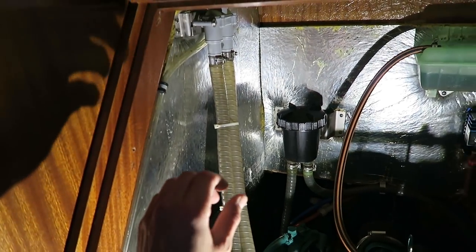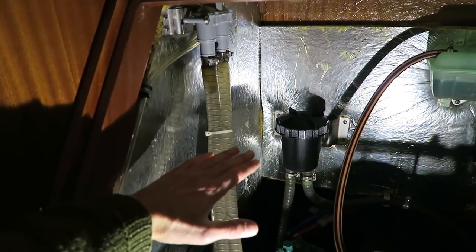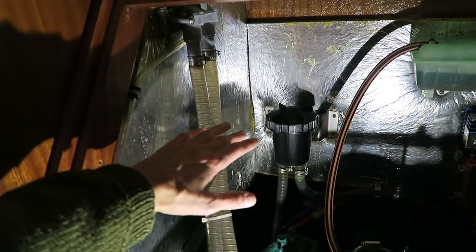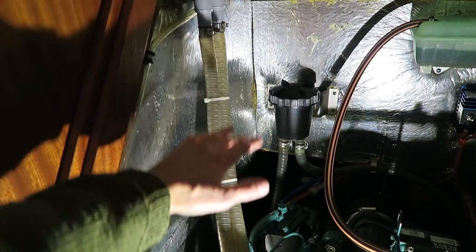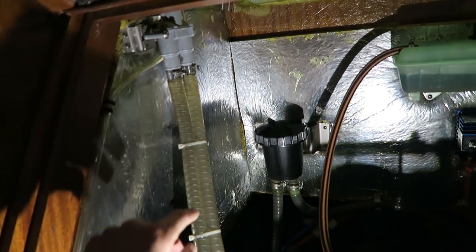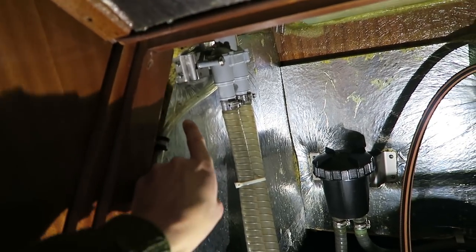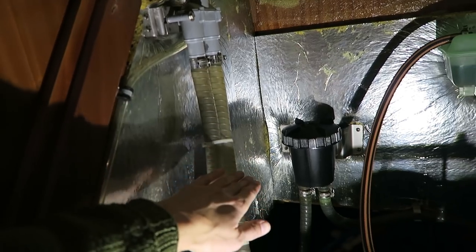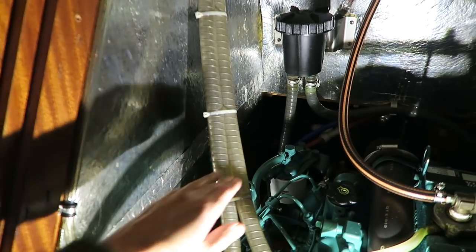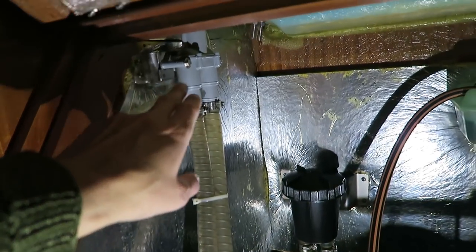When you turn off the engine, both pipes must drain slowly. The siphon valve must then let in some air through the hose and the system will drain. If water is coming out of the hose here, the valve is stuck or something is wrong.